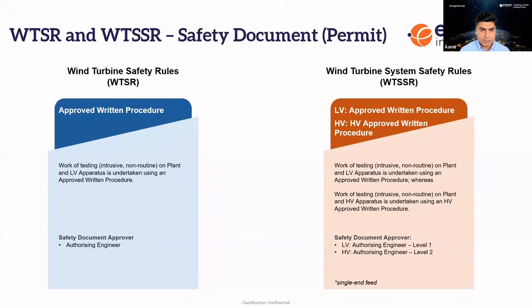Isolation and safety precautions will require a HV approved written procedure, which will be led by an authorized technician level 2, and the document will be created and approved by an authorizing engineer level 2. The HV approved written procedure can have elements of both permit to work, as often referred to under the high voltage safety rules, as well as sanction for test.